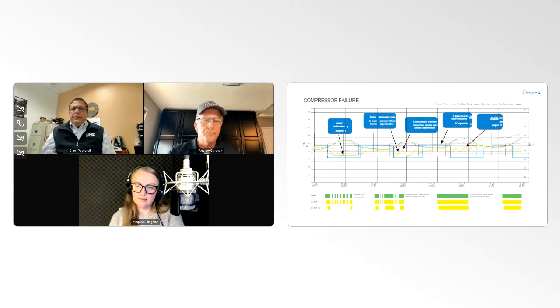For example, prior to heating season, looking at a gas-fired rooftop, the burner and ignition system should be inspected. Like, for example, talk about a whole bunch of different electrical components: the venter motors, pressure switches, flame sensors. There are several electrical components that make up a burner system, which all potentially could fail during the heating season. That just gives you an example of how highly integrated these are. And all it takes is just for one electrical component to fail. And then all of a sudden now you have either no heating or no cooling.